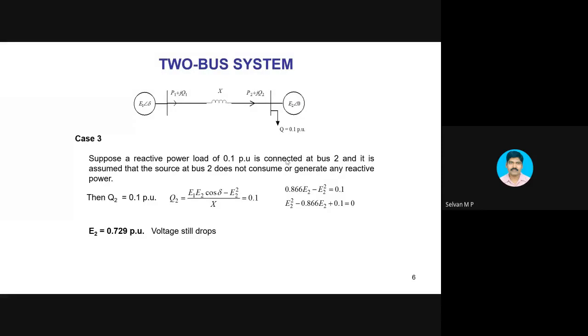This will happen for a long time, but at one point of time, the source which is connected at the sending end will exhaust its capability to supply reactive power, because it is a physical machine. Let it be a synchronous machine. Though it is capable of supplying real and reactive power, it has certain capability. It cannot supply beyond its rating. A 500 MVA generator can supply only 500 MVA.